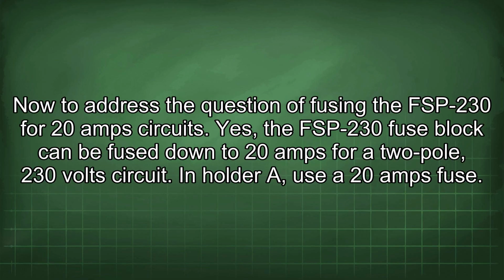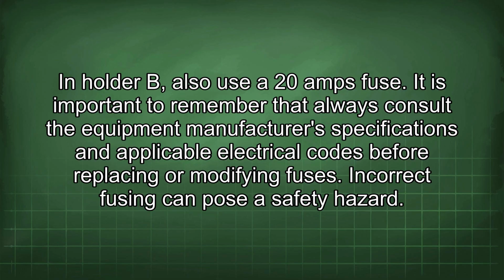Now to address the question of fusing the FSP-230 for 20 amp circuits. Yes, the FSP-230 fuse block can be fused down to 20 amps for a 2-pole, 230 volt circuit. In holder A, use a 20 amp fuse. In holder B, also use a 20 amp fuse. It is important to always consult the equipment manufacturer's specifications and applicable electrical codes before replacing or modifying fuses. Incorrect fusing can pose a safety hazard.